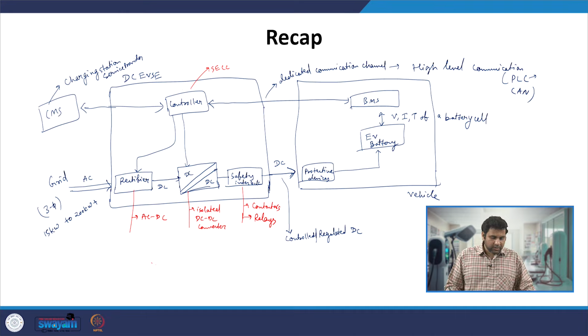So they require a dedicated communication channel. Since a continuous stream of data has to be shared between the EVSE and the EV, they follow high level communication done via PLC. For example, in the CCS2 charging system they follow PLC, while in some charging systems they follow CAN communication. CAN is controller area network communication, and PLC means power line communication. The output DC is controlled DC, with voltage and current as demanded by the vehicle controller.